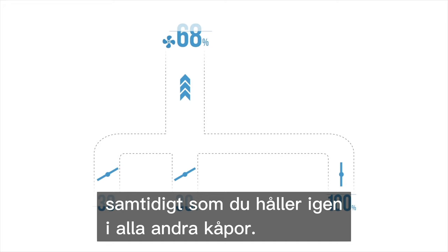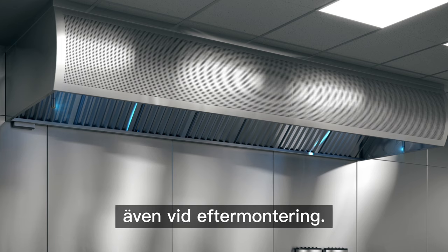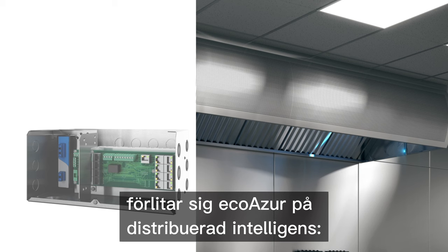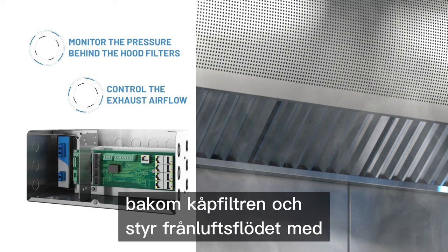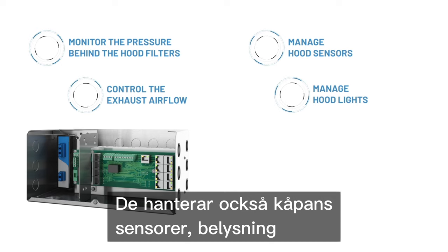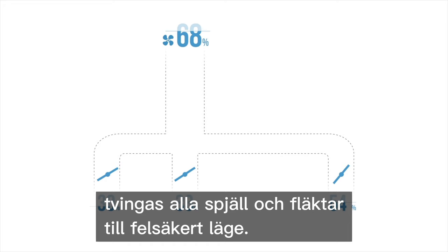The damper's unique retractable design requires no cutting and no welding of greasy ducts. They are safe and simple to install, even in retrofit applications. In order to orchestrate such innovative damper technology, ecoAzur relies on distributed intelligence: the HC hood controllers. These compact controllers continuously monitor the pressure behind the hood filters and control the exhaust airflow using the modulating dampers. They also manage hood sensors, hood lights, as well as supply air VAV boxes. Should a fire occur or a VFD system be switched to bypass mode, all dampers and fans are safely forced to their fail-safe states.